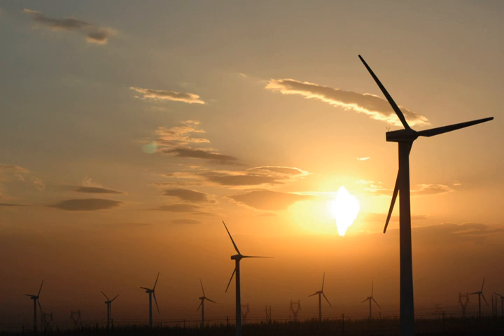Studies have indicated that 20% of the total annual electrical energy consumption may be incorporated with minimal difficulty. These studies have been for locations with geographically dispersed wind farms, some degree of dispatchable energy or hydropower with storage capacity, demand management, and interconnected to a large grid area enabling the export of electric power when needed. Beyond the 20% level, there are few technical limits, but the economic implications become more significant. Electrical utilities continue to study the effects of large-scale penetration of wind generation on system stability and economics.